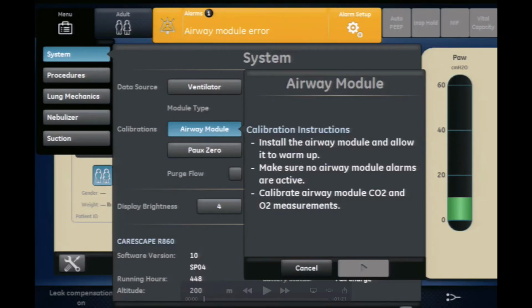One of the indications for airway module calibration is if you have continuous airway module error alarms. One should first try to troubleshoot the alarm by looking at the gas sampling line. It may be occluded by water or the water trap itself. The other indication for airway module calibration is that it has met its calibration date, which is every 2 months.